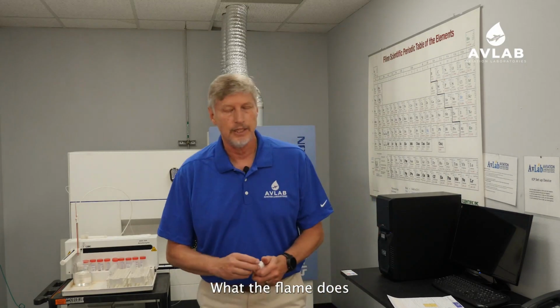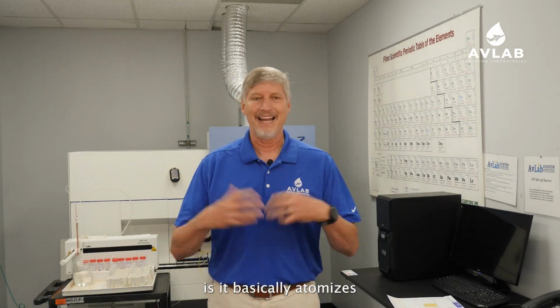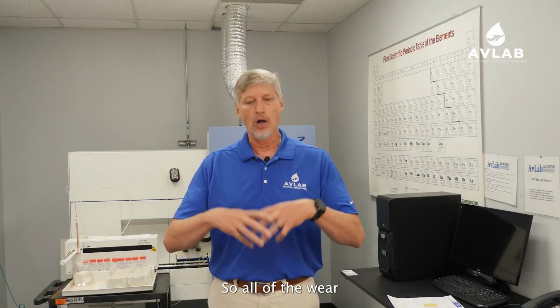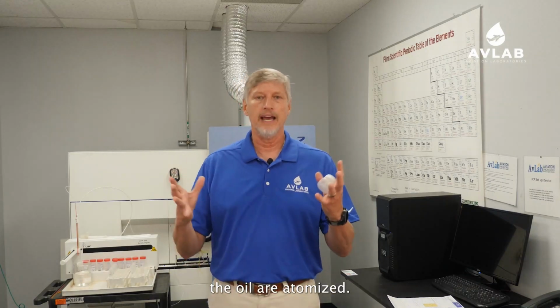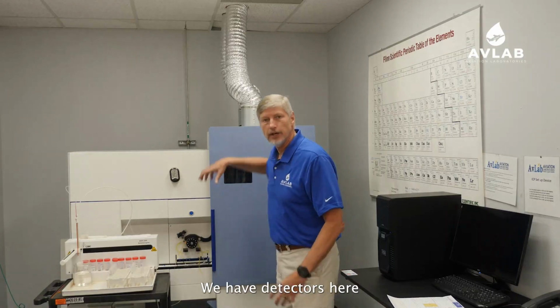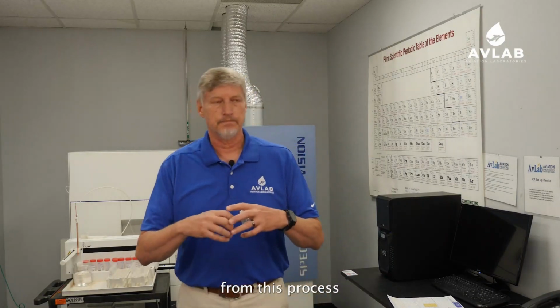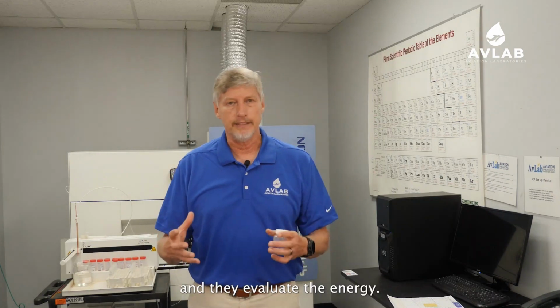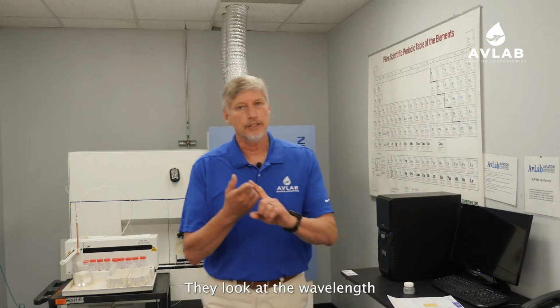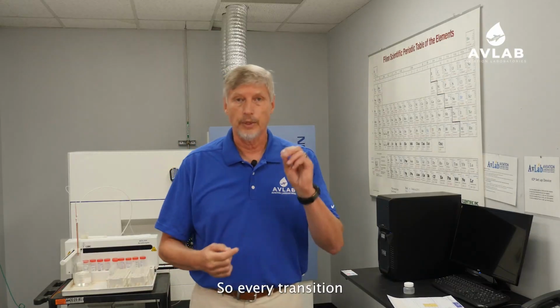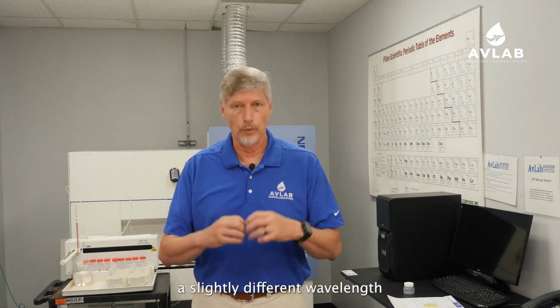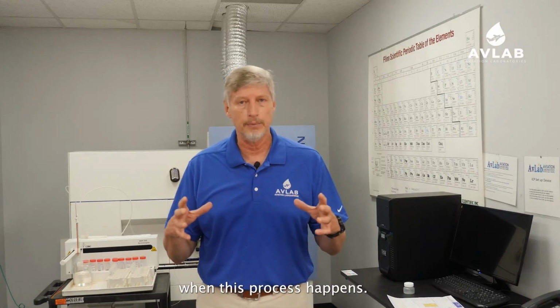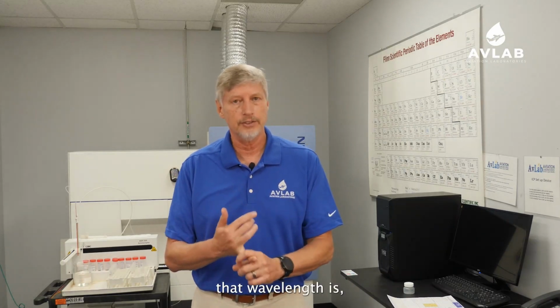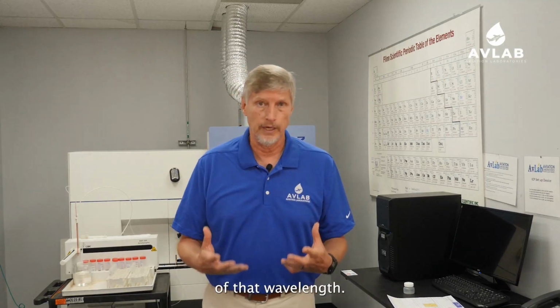What the flame does is it basically atomizes all of this oil. So all of the wear metals that are in the oil are atomized. We have detectors here that pick up the energy from this process, and they evaluate the energy. They evaluate it for 2 things. They look at the wavelength of a particular metal. Every transition metal has a slightly different wavelength when this process happens. So it picks up on what that wavelength is, but it also picks up on the strength of that wavelength. The strength of the wavelength tells us how much of that metal is in the oil sample.